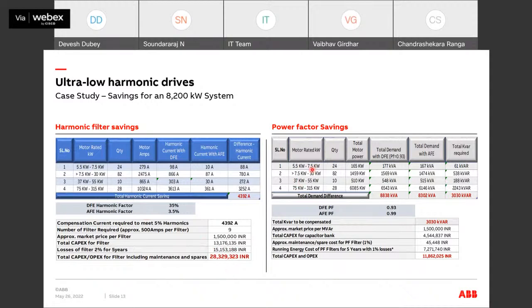Similar with the power factor. When we see any diode front-end drive, the power factor, as I told you, will be in the range of 0.93. When we have active front-end drives, the power factor will be unity. We have calculated the differential between the total demand with the DFE and the total demand with the AFE. For the same rating of 8.2 megawatt, it comes to near about 3000 kVAR. Power factor compensation is needed. For that, considering 1.5 million per MVAR, the total capex for the capacitor bank is going to be 4.5 million.